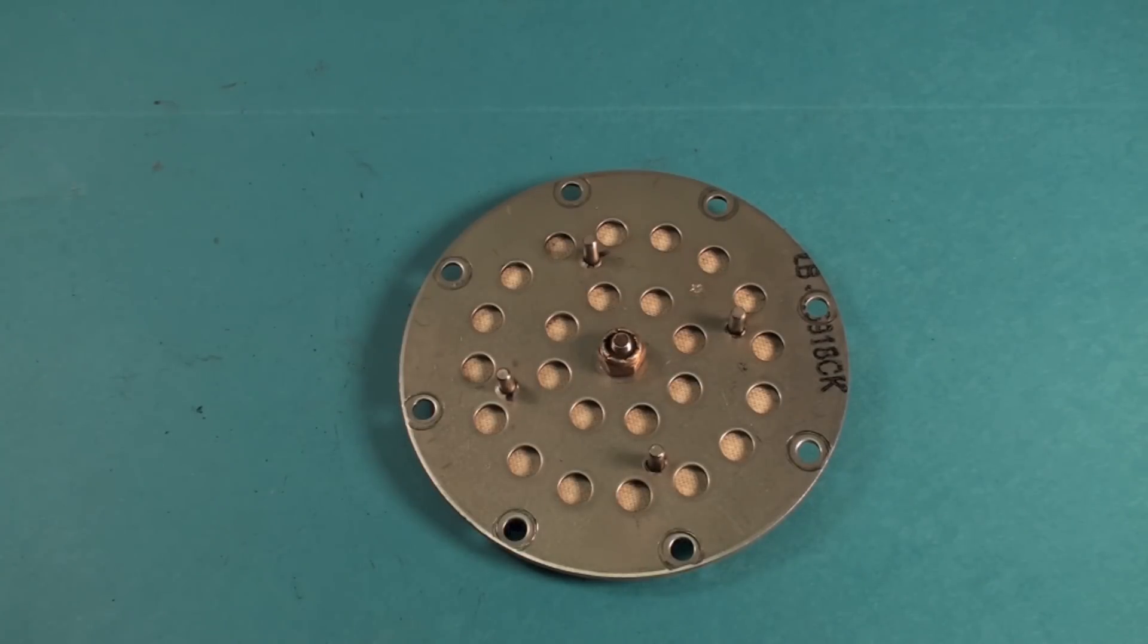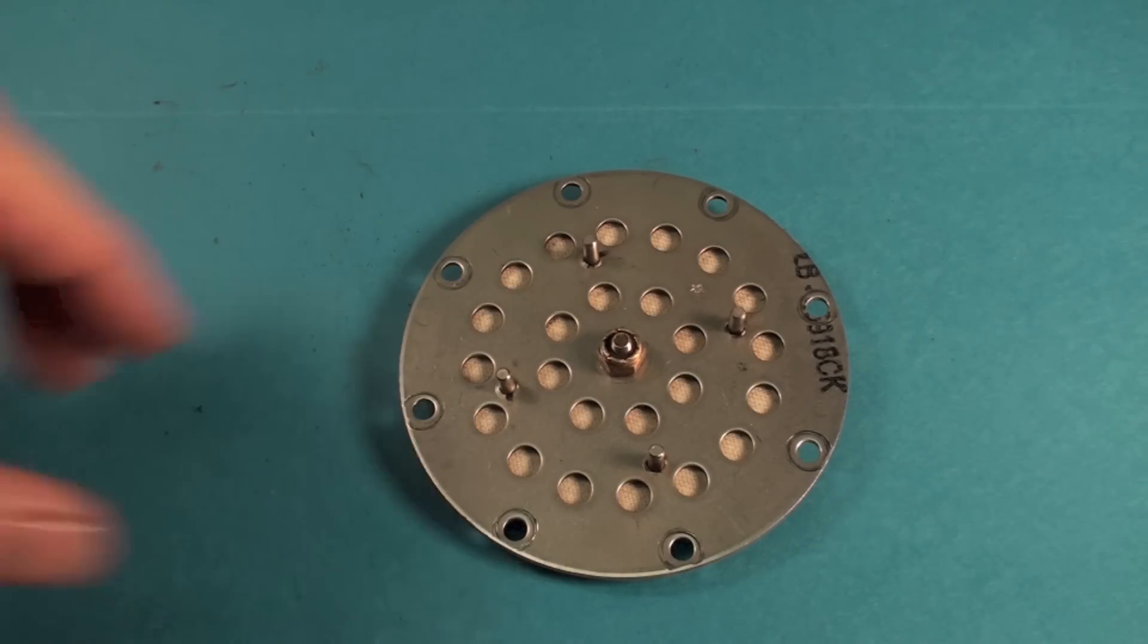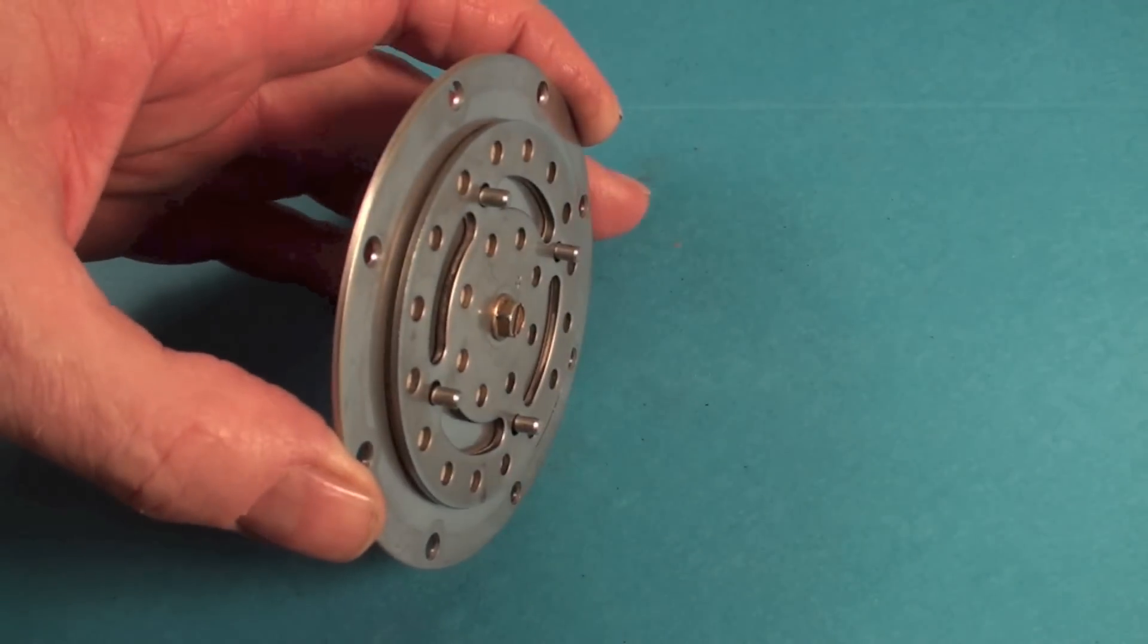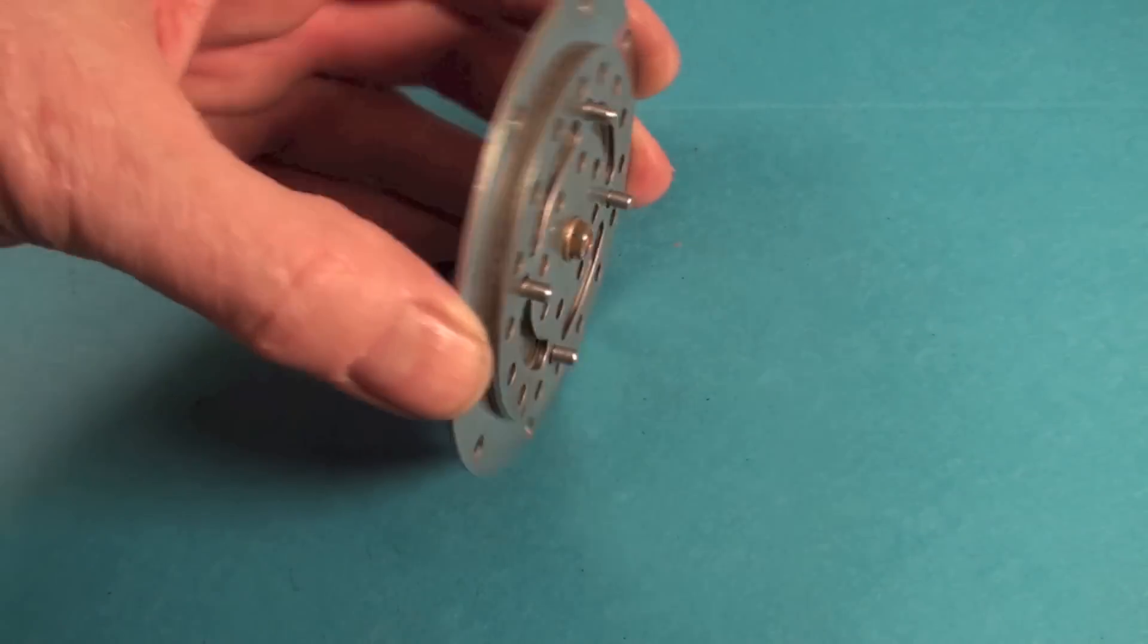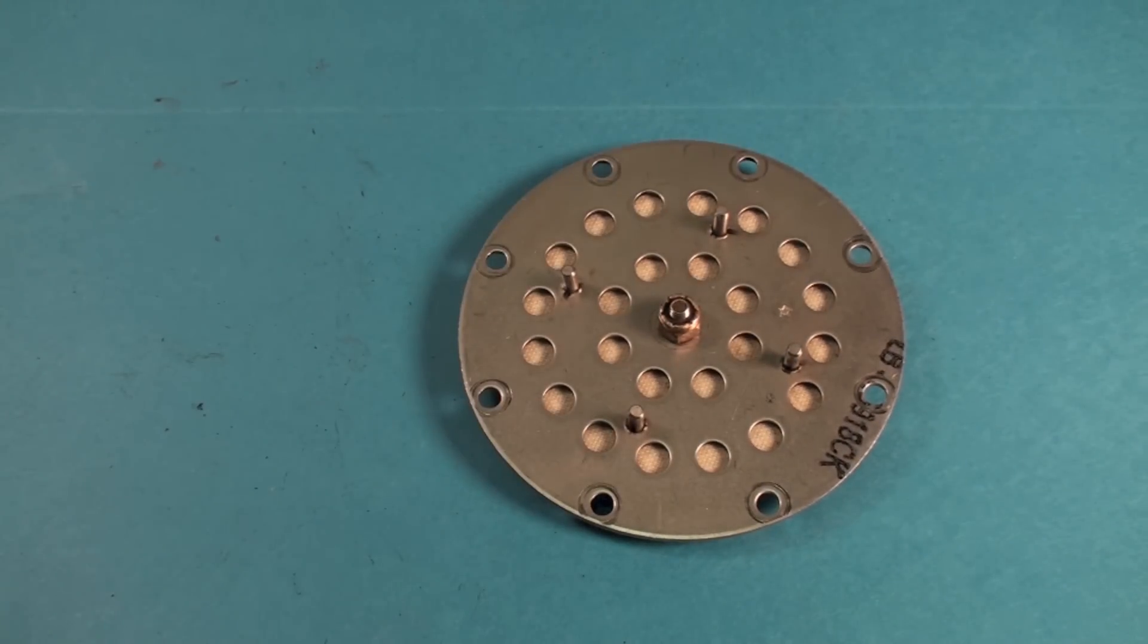I've been told by some guys these things should be replaced every year. I never did that. It was more like three to five years that those flappers were replaced on that I saw. Anybody out there that has different experience, love to hear about it. But anyway, that's the air flapper, not the gas flapper. I'll show you the gas flapper in another video.